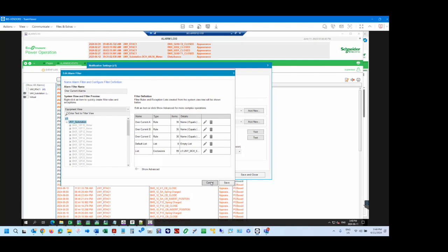Similarly, going forward too, if we are going to do some type of load shedding activities, I need to know what L56 plus L57 are, to make sure that as long as these two are below 55 megawatts, we do not need to incorporate demand response. But if it goes above 55 megawatts, I may need to incorporate the demand response. So that would send out an alarm notification. Above 55 megawatts, yeah. So that's a couple of examples. The other one I mentioned is done now because that was during one of the construction phases, but the 55 megawatts is the real one.